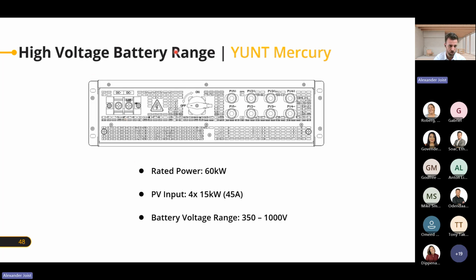Just a quick view on the MPPT. The MPPT has got 4 inputs, so it's 4 times 15 kilowatts, but it's only 1 MPPT. Make sure that 60 kilowatts must be one direction, it can't be 4 different directions. It's not 4 MPPTs, it's 1 MPPT with 4 inputs of 15 kilowatts each.